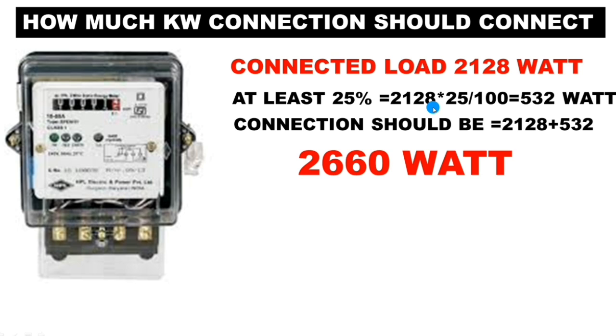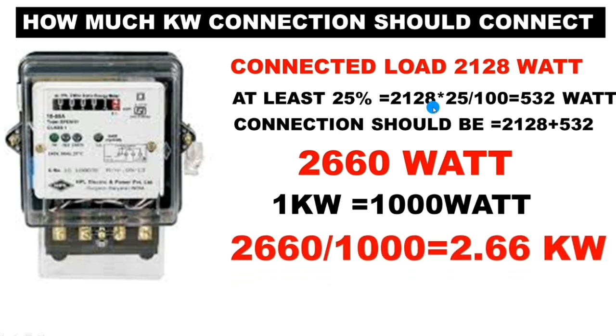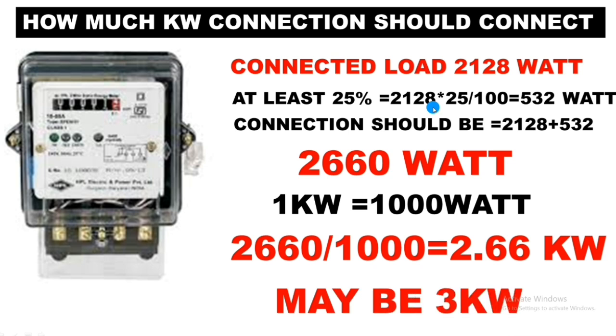We find 2660 watts. Since 1 kilowatt equals 1000 watts, divide by 1000 to get 2.66 kilowatt. So for this load you should take an energy meter of approximately 2.66 kilowatt maximum demand. If you think your equipment will increase in the future, you can take approximately a 3 kilowatt energy meter. I hope the concept is clear. If you like this video please press the like button, and if you have any query please ask in the comments. Thanks for watching.